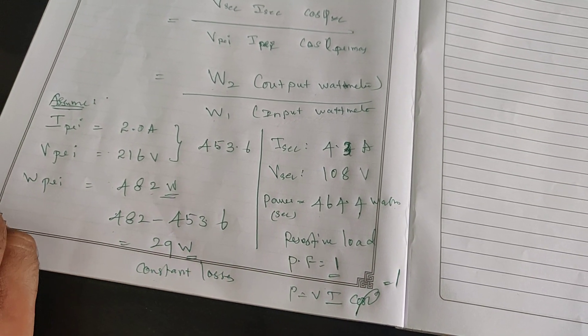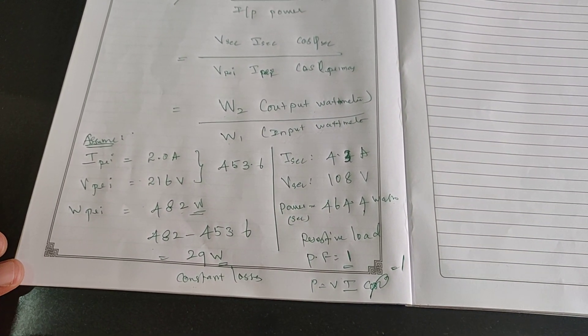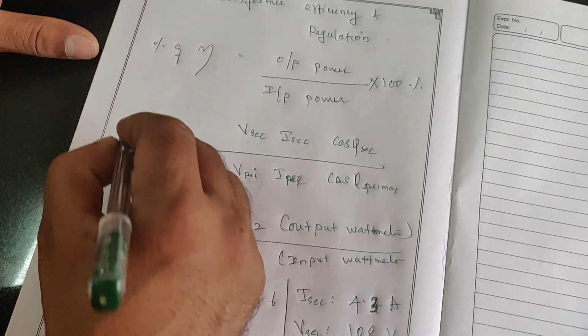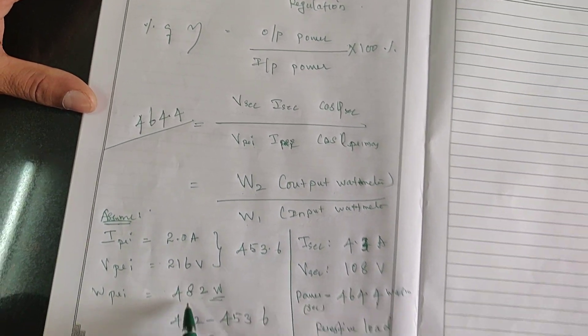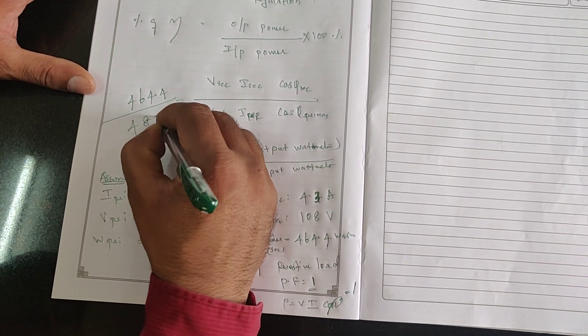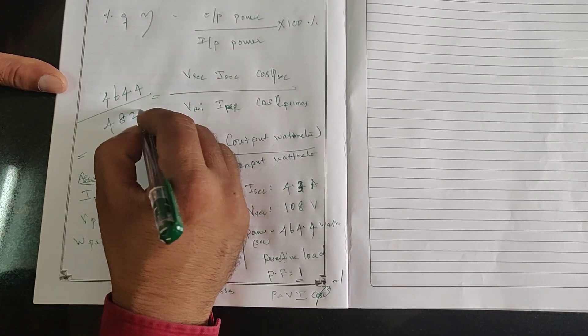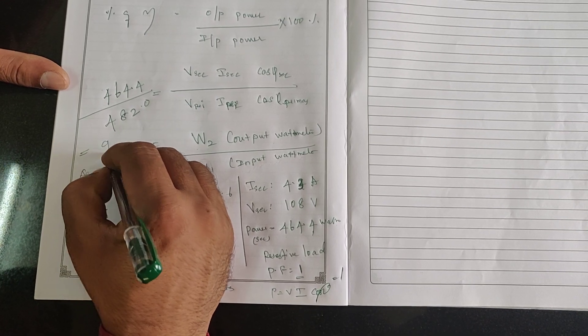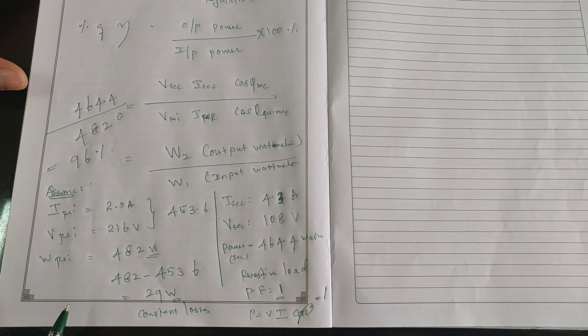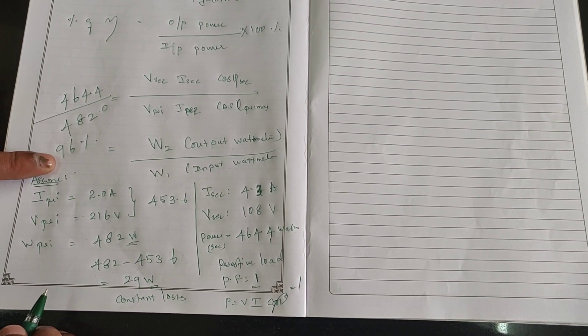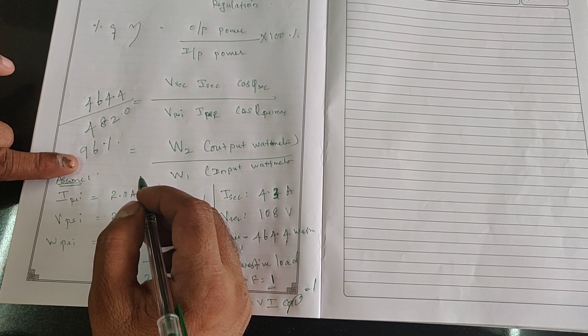Therefore, the efficiency is now calculated: this is the output side and this is the input side — output divided by input. Output is 464.4 watts and input is 482 watts. Therefore, the efficiency of this transformer is approximately 96%. In any transformer, the output efficiency should not be less than 90% or 95%.